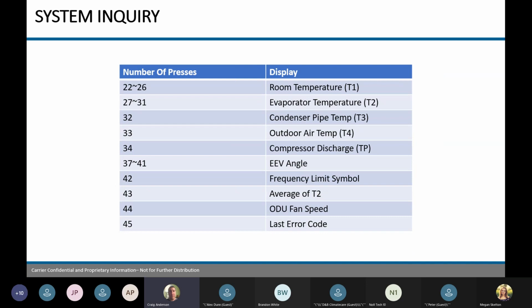So we can get up to a number of presses. You're going to have to press that little button 33 times to get the outdoor air temperature. It is what it is. If that's what needs to be done on a job site, then we press it 33 times to make sure that sensor is working properly.